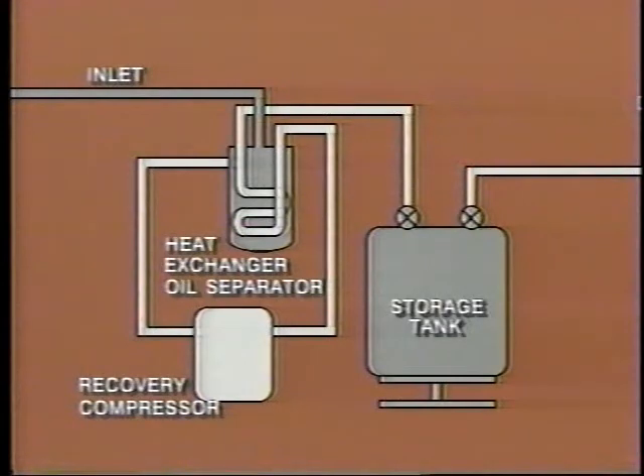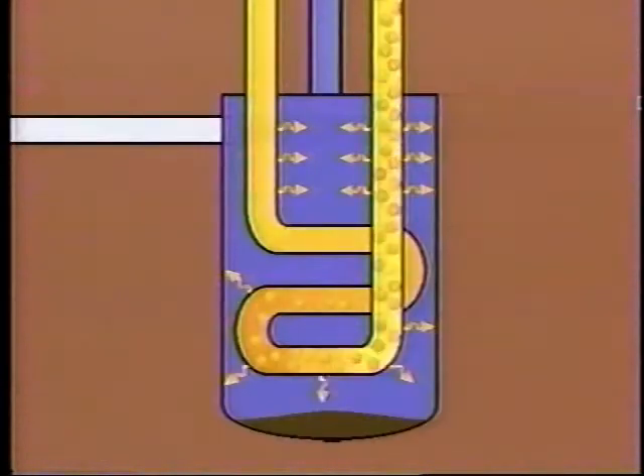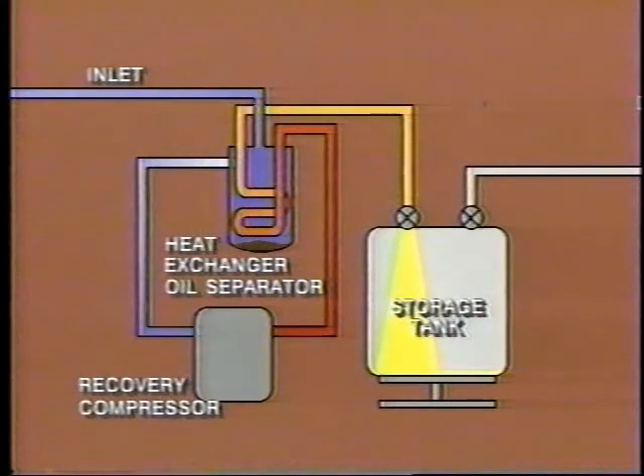When the recovery compressor runs, R12 gas flows from the inlet to the heat exchanger oil separator. Refrigerant oil and moisture simply fall from the R12 gas and collect on the bottom. This is the initial cleaning step. The recovery compressor pumps the R12 gas back to the heat exchanger as a hot gas, which is about 150 degrees Fahrenheit. The heat exchanger coil draws heat from the hot R12 gas, changing it to hot liquid.